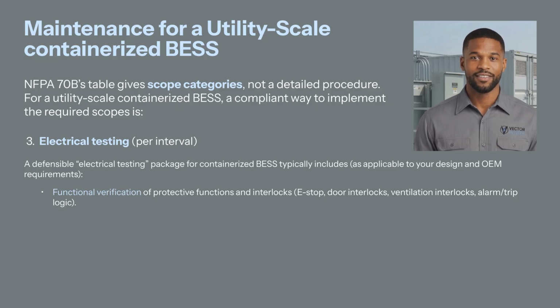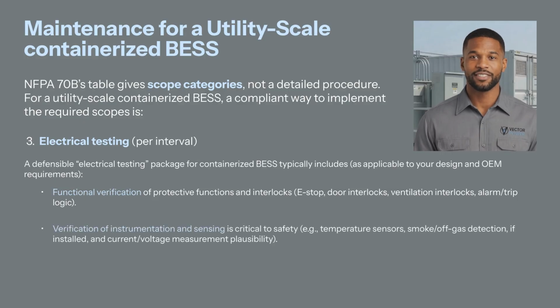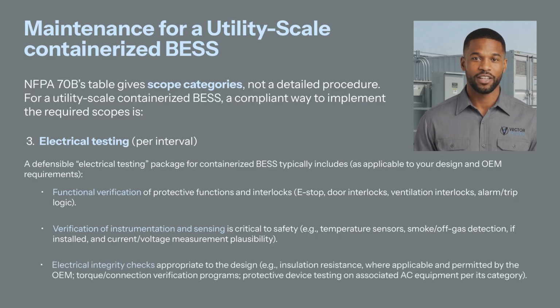Verification of instrumentation and sensing that is critical to safety, for example, temperature sensors, smoke and off-gas detection if installed, and current and voltage measurement plausibility. And electrical integrity checks appropriate to the design, for example, insulation resistance, where applicable and permitted by the OEM, torque connection verification programs, protective device testing on associated AC equipment per its category.